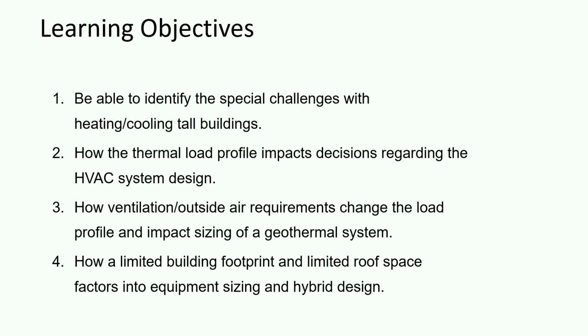We're going to talk a little bit about the thermal load profile, because that's the foundation for all design, really understanding what that thermal profile looks like throughout the year, and then long term, when we're talking about geothermal, how it impacts the ground and the bore field. When you start to get tall buildings, it's amazing. Even in New York City, you flip from a heating dominant application to generally a cooling dominant application, which is extremely important when related to geothermal, right? Because with the limited ground area, if we're putting a lot of heat in the ground, how does that impact the ground over the long term? And so we've got to look at that.